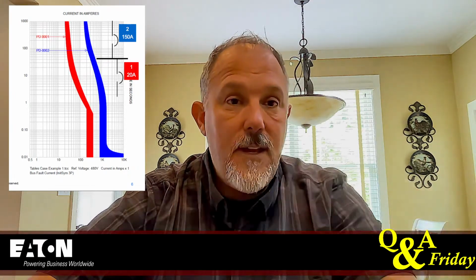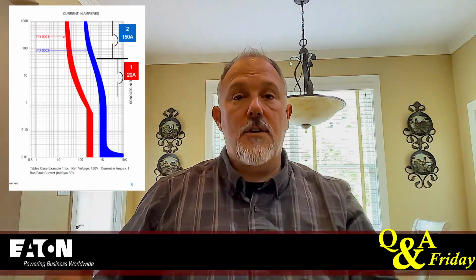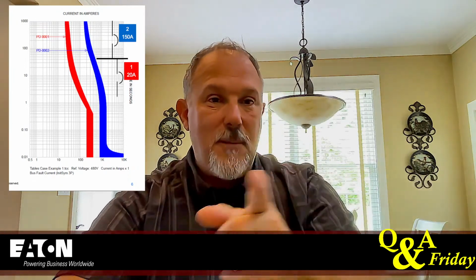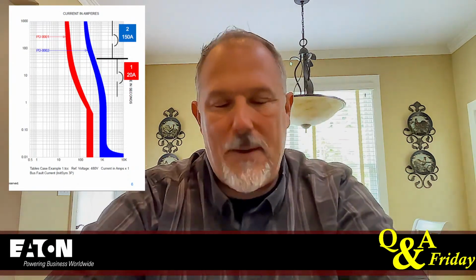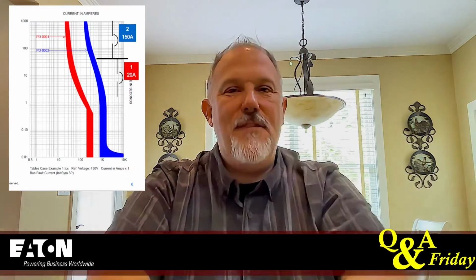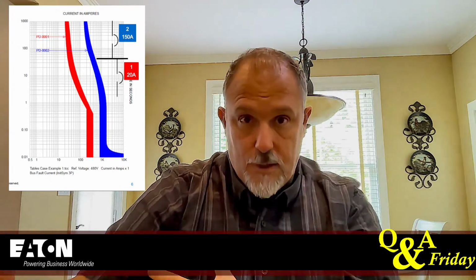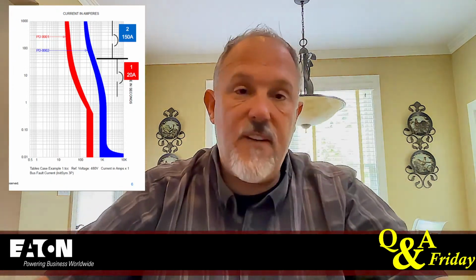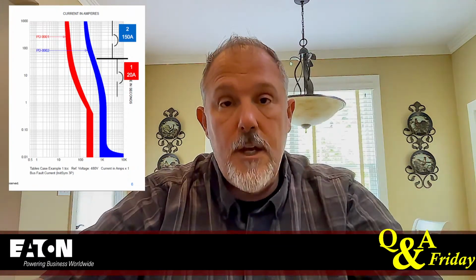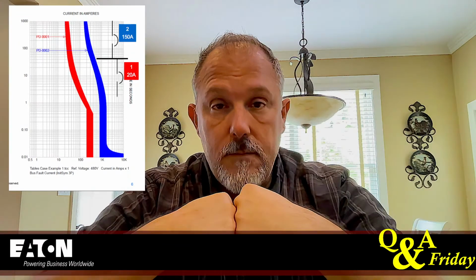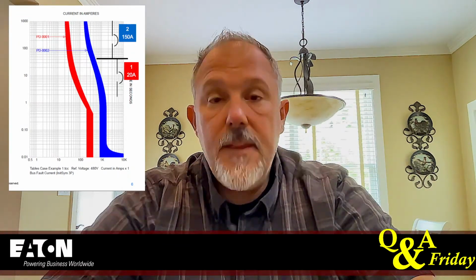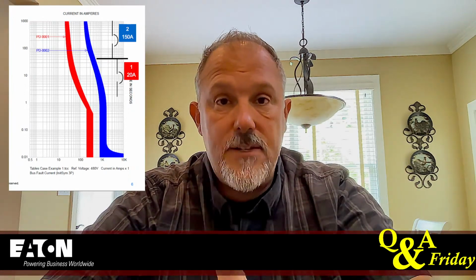Say you have to put in 250 amps worth of conductor, because that's the lowest you can dial that larger frame breaker down to. Now you're feeding the equipment, which used to be a 150 amp panel. Now you have to put in a 400 amp panel, or a 250 amp panel, whatever that new number is. So you have now increased the size of the infrastructure. And why is that? Is it because you have more load? No, it's just because you need those contacts to stay closed for those high fault currents. So that's the challenge when you start to try to address selective coordination and put larger devices upstream.